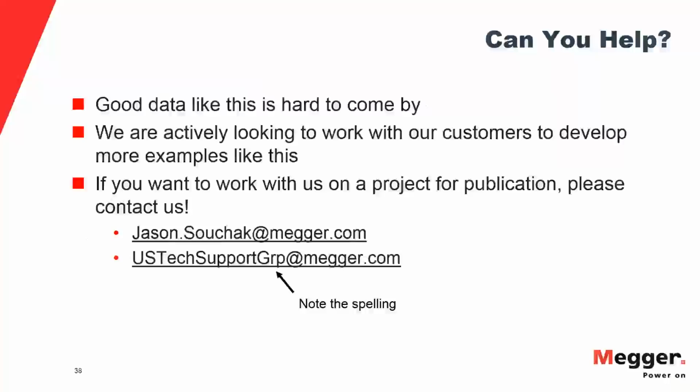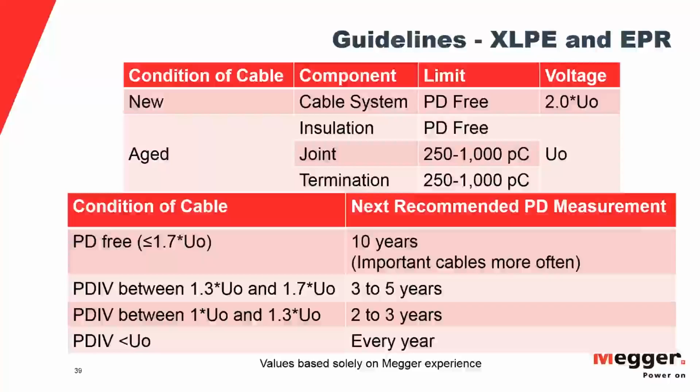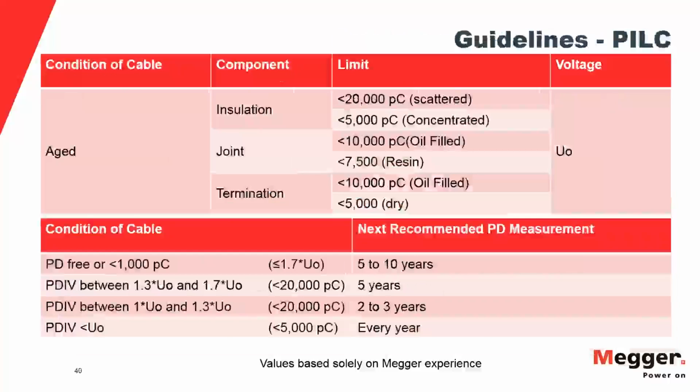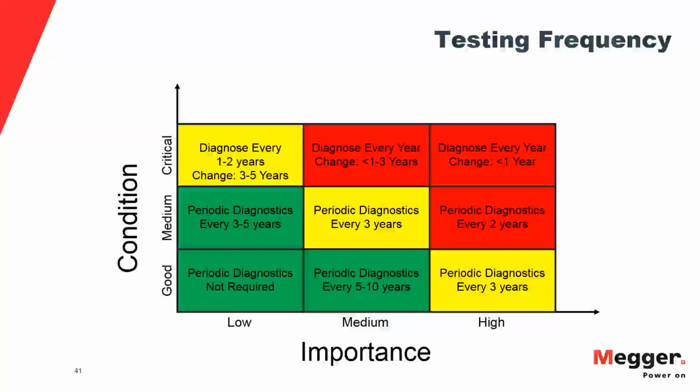The TDS follows this requirement. So that is the frequency that you can apply with the DAC. So the DAC portion of the TDS fully complies in any aspect, calibration, measuring, application of the voltage and everything with the IEC standard, and the 0.1 hertz VLF portion. So when you just do the withstand, it complies with the VDE, the CENELEC, the IEC, and the IEEE 400.2, also with all the international standards as well.